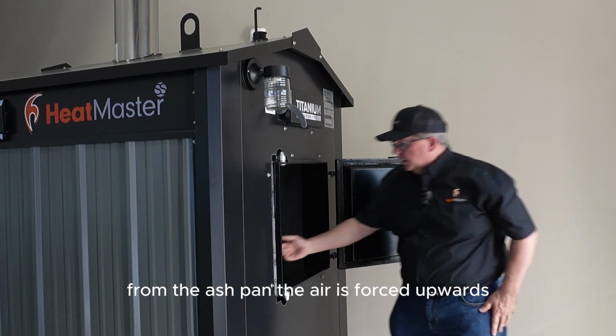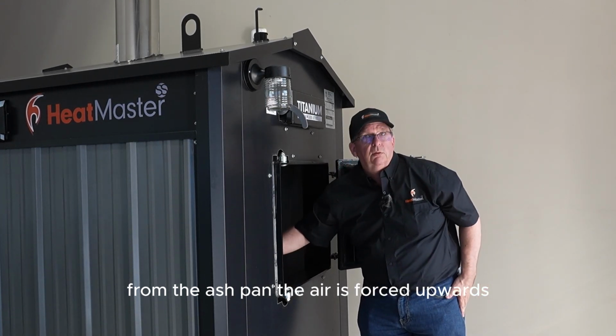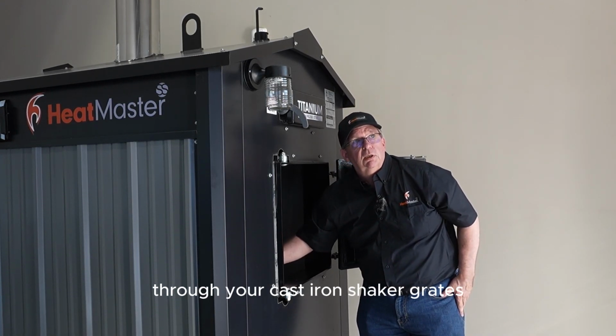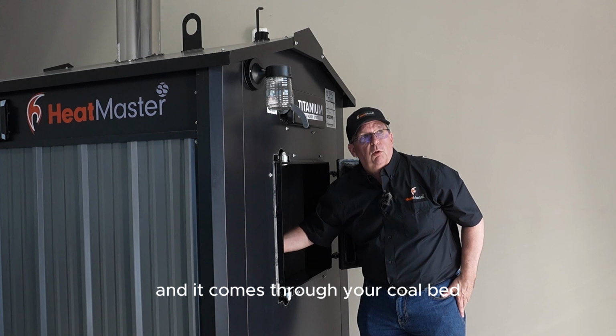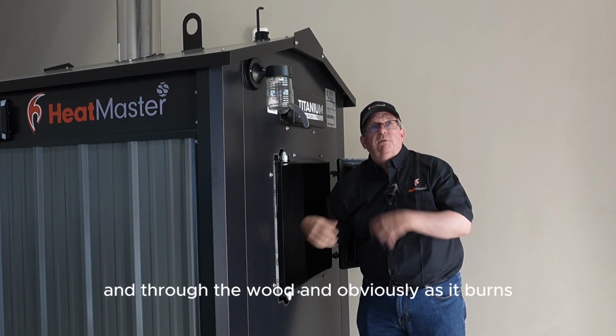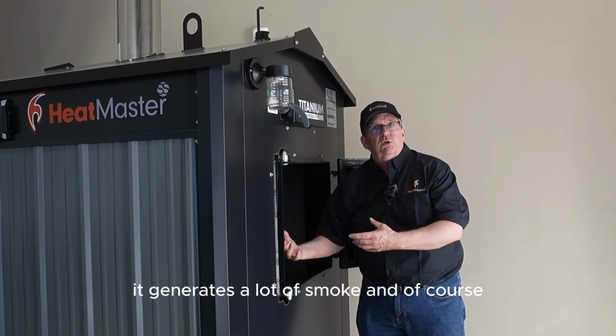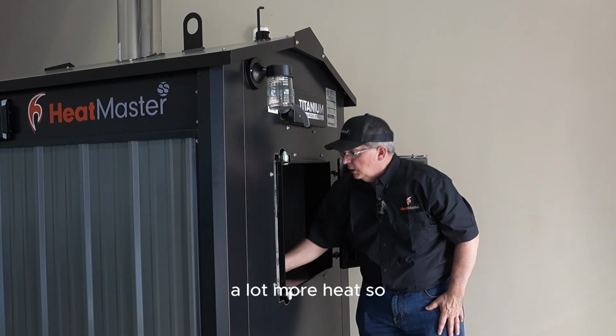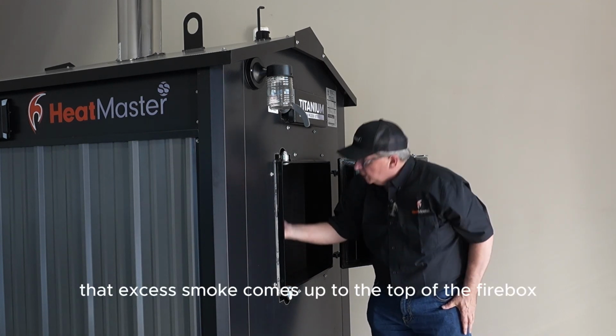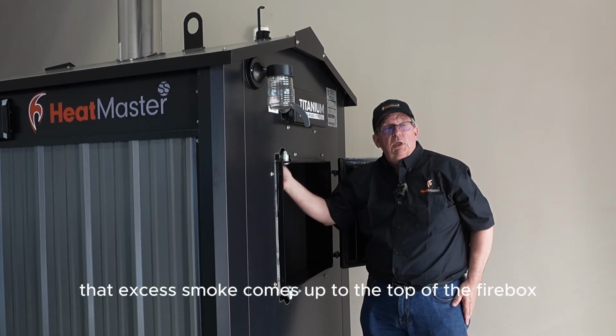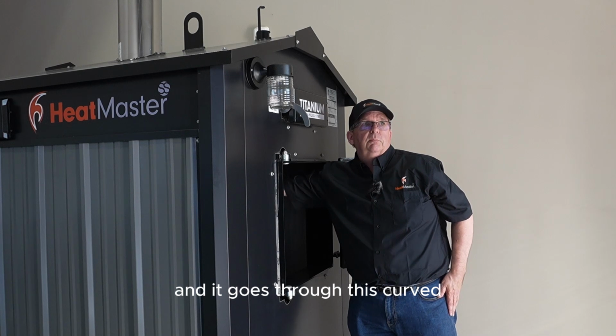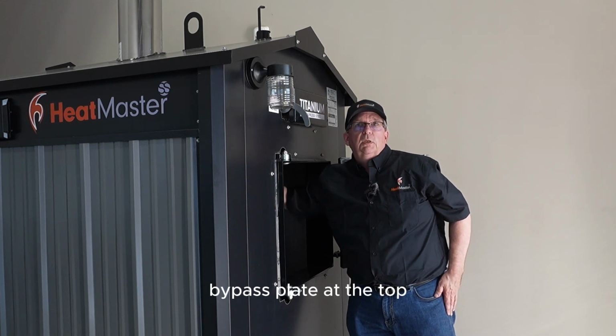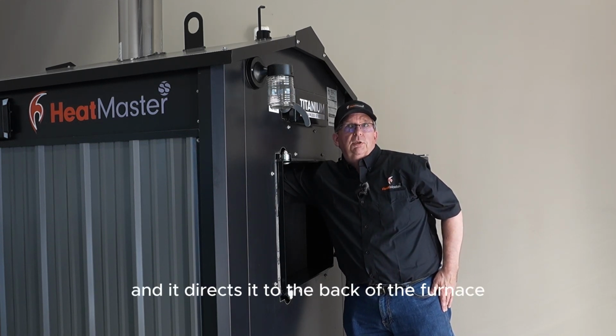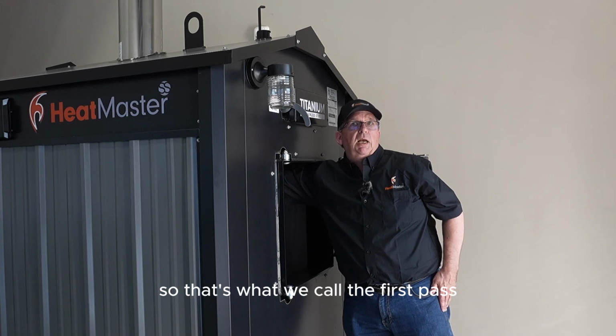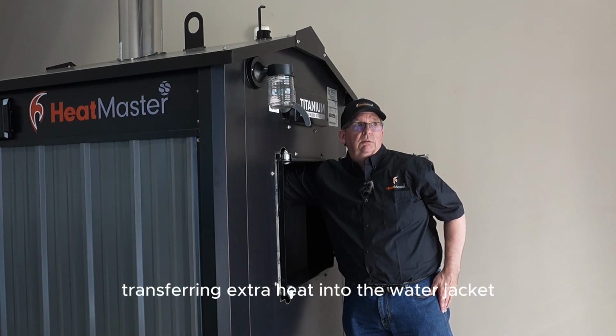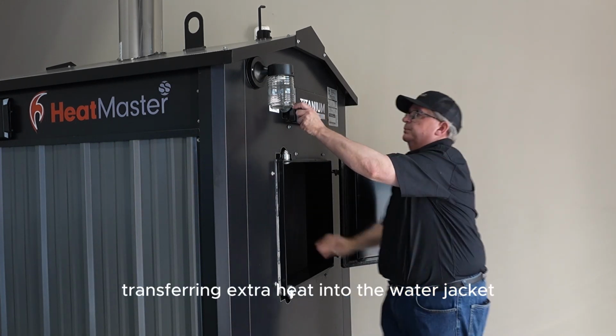From the ash pan, the air is forced upwards through your cast iron shaker grates, and it comes through your coal bed and through the wood. And obviously, as it burns, it generates a lot of smoke and, of course, a lot more heat. So now that excess smoke comes up to the top of the firebox, and it goes through this curved bypass plate at the top, and it directs it to the back of the furnace. So that's what we call the first pass, where it begins transferring extra heat into the water jacket.